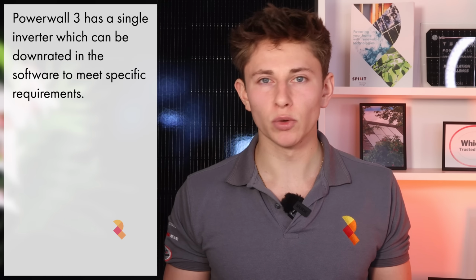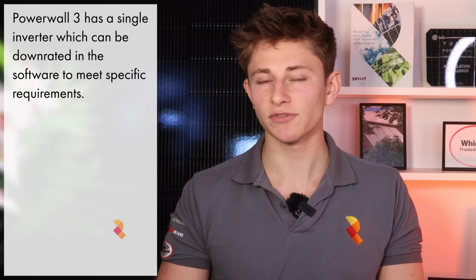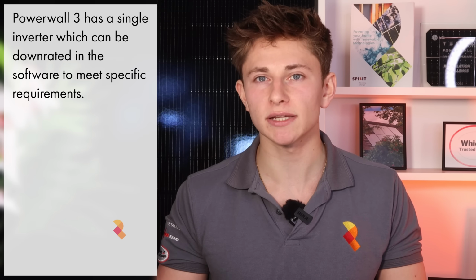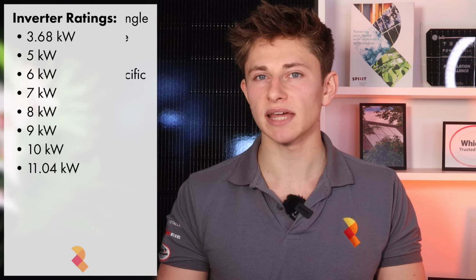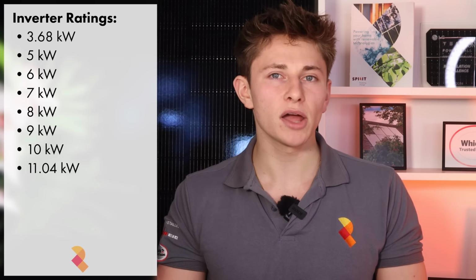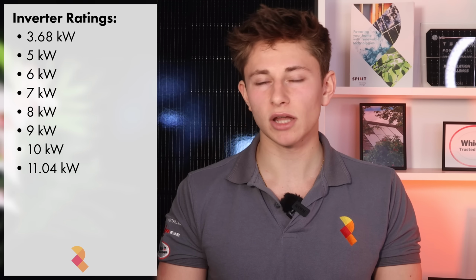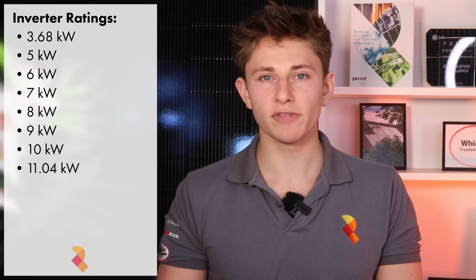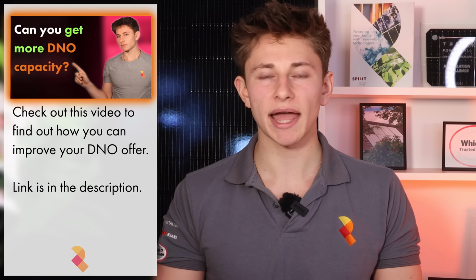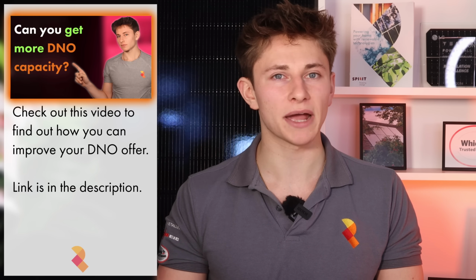If for whatever reason you're not permitted to install the inverter at its full 11.04 kilowatt inverter rating, then it can be throttled down and set to any of 3.68, 5, 6, 7, 8, 9 or 10 kilowatts without any of the hardware needing to be changed. A big advantage to Powerwall 3 is that because the inverter rating is set in the software instead of dictated by the built-in hardware, it can be remotely uprated down the line if your DNO offer increases. See our YouTube video talking about how to get a higher DNO rating to learn more about this.